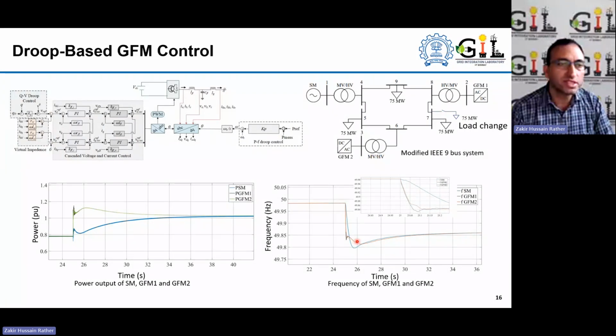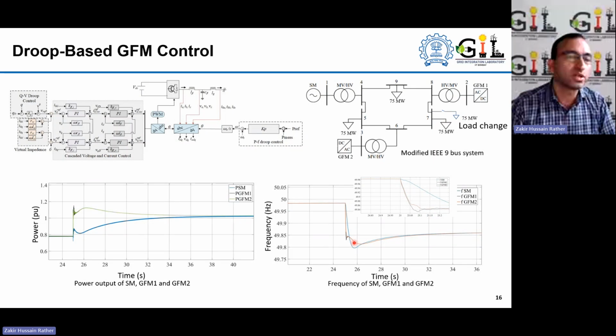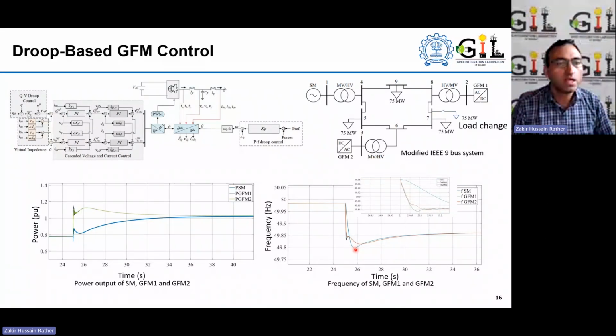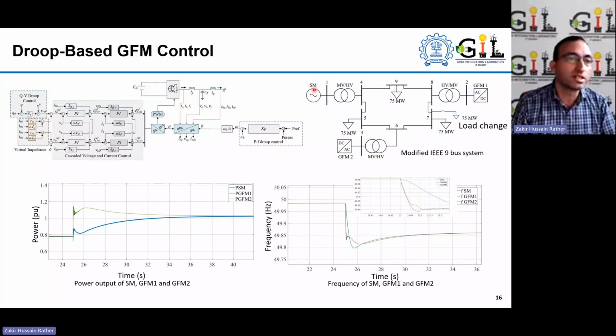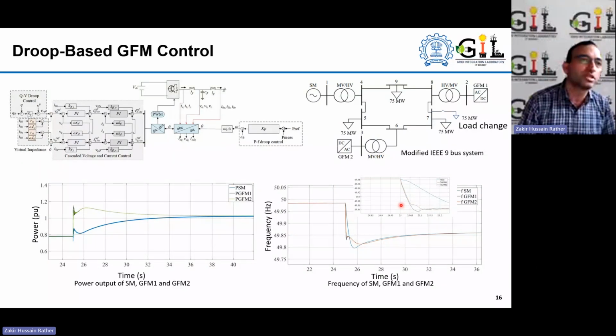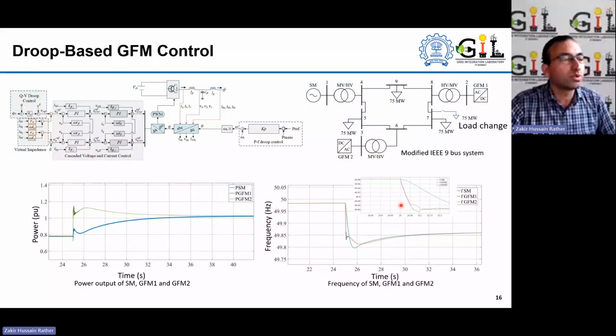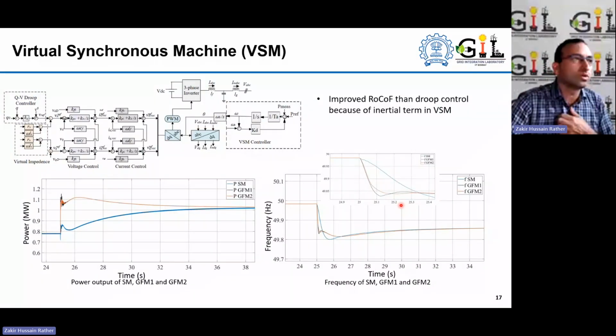What we can see here is that the frequency nadir is improved because of this grid forming technology. However, if you look at the conventional generator, its nadir goes relatively lower. But the rate of change of frequency, the RoCoF, is better, improved in the case of the conventional generator, because of the inherent inertia that it provides, whereas it's not as good in the grid forming case because it does not provide the same response in terms of inertial control.